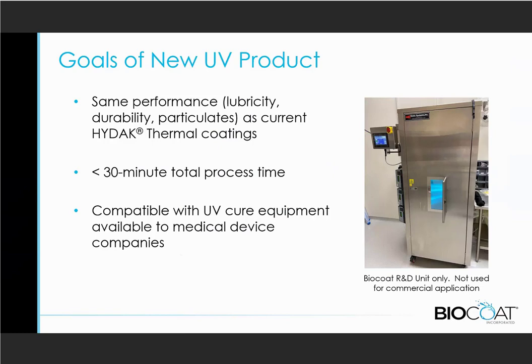One of the issues with a thermal cure system is that it takes a little longer to cure. So we wanted to reduce that process time to less than 30 minutes for the entire process, from the coating through the curing. As I said, the thermal system can take a little bit longer than that. But we also wanted to ensure compatibility with UV cure equipment that is available, or sometimes even already installed at some medical device companies, so that people can rest assured that what we're developing doesn't change the investment they've already made in their coating equipment. That's being done with these UV flood lamps, which you can see on our prototype coating system here.